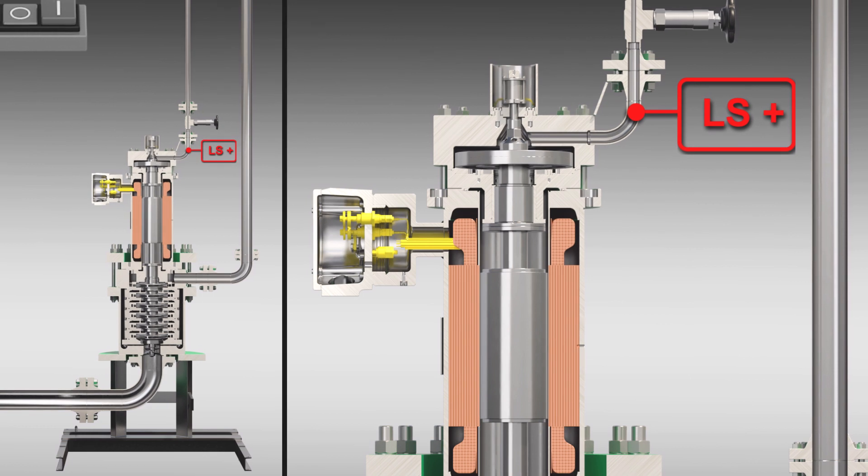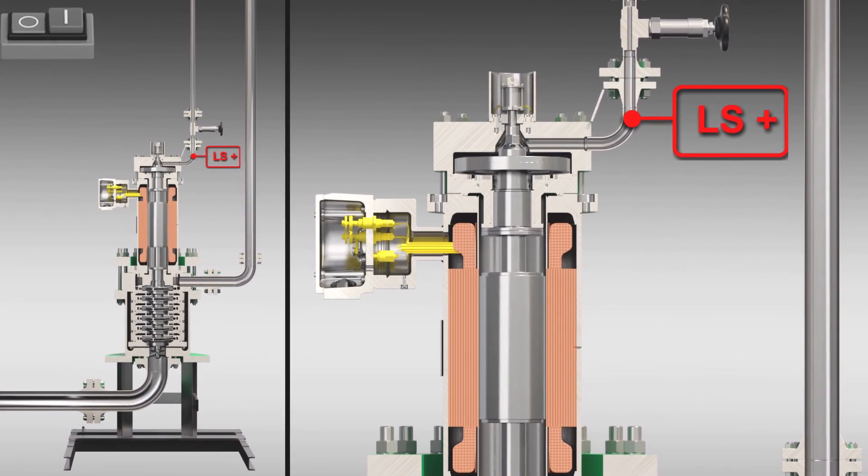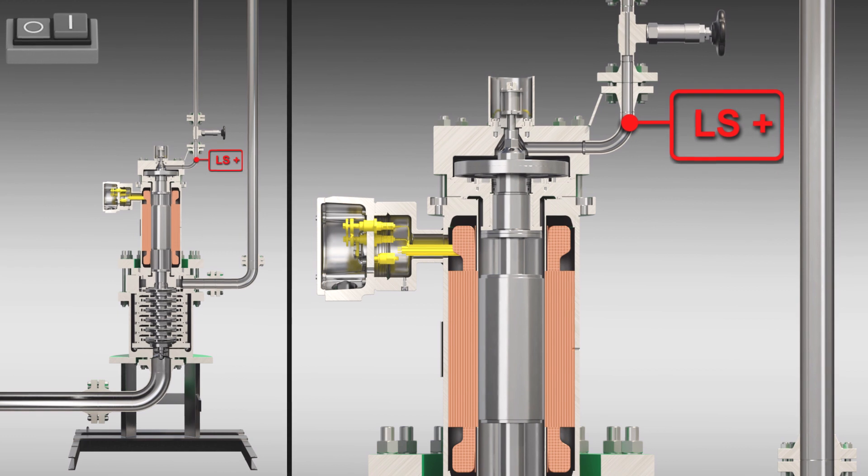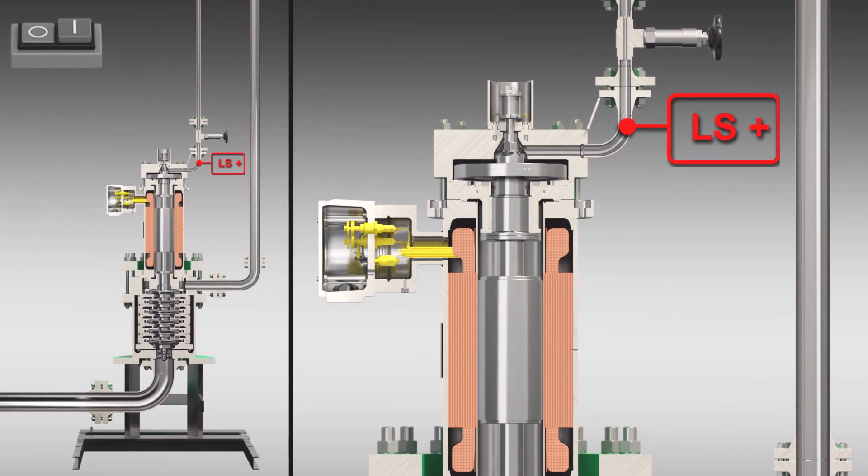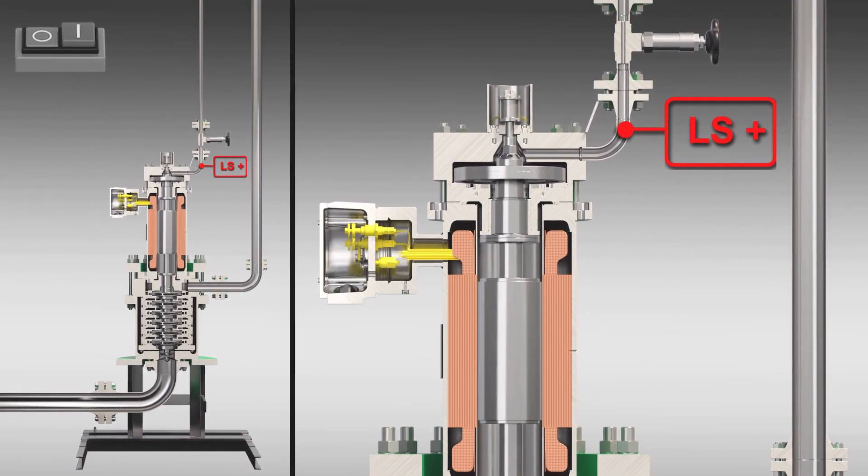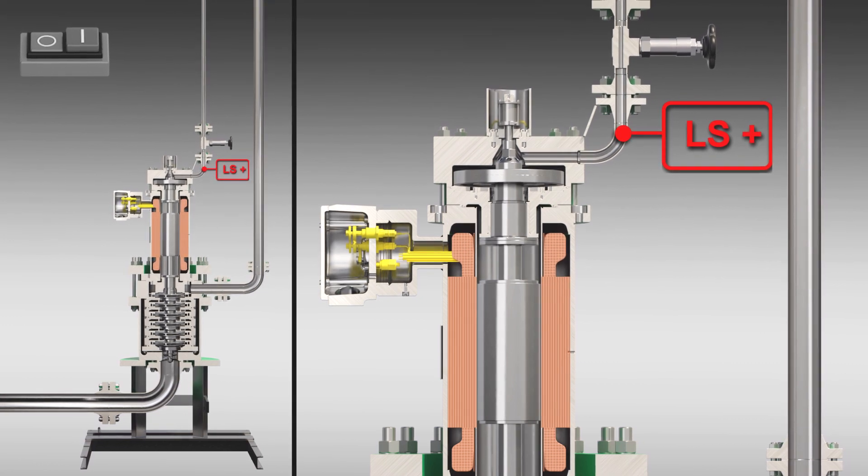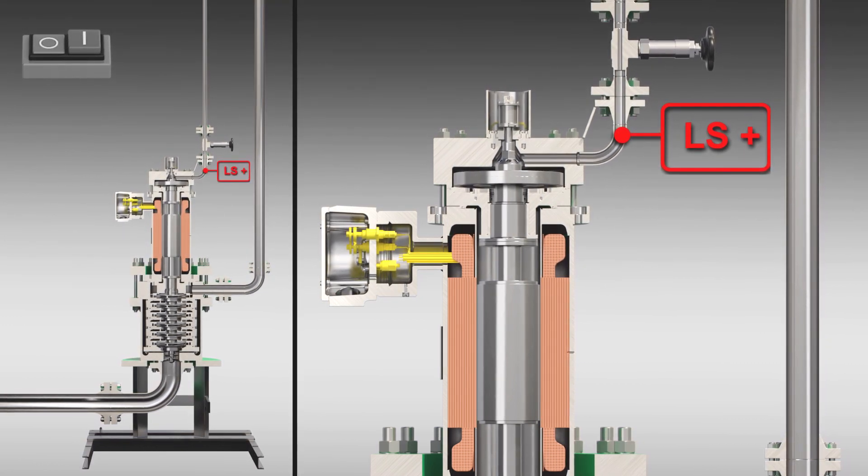The hydrodynamic slide bearings only perform a guiding function in the vertical installation. This is an advantage, especially with very low viscosities, because they no longer have a load-bearing function. The bearing weight is carried hydrodynamically in operation.